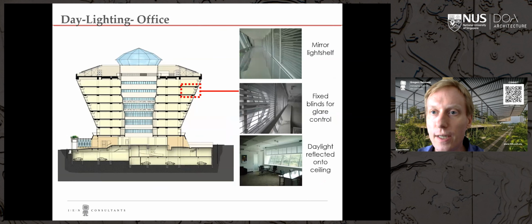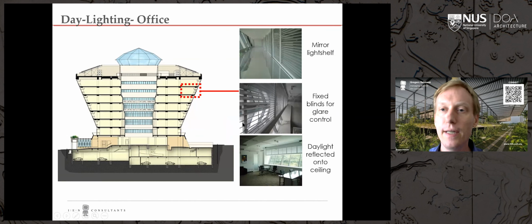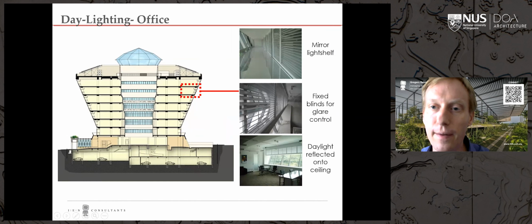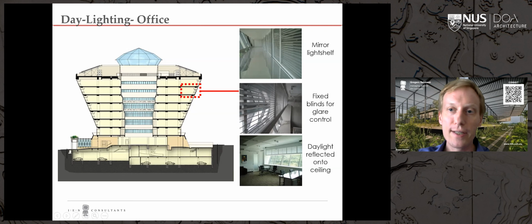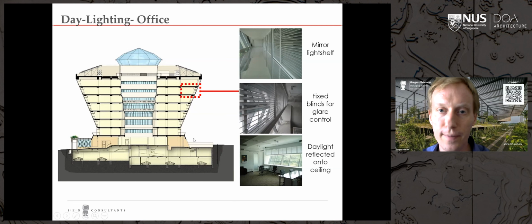Here's some photos of this light shelf design. And on the middle photo here, you can see we deliberately designed it so the windowsill protrudes about 300 millimeters further than the light shelf. So therefore, you can easily walk on this windowsill, take out a few of these louvers and go and clean the light shelf with a cloth when needed, because of course some dust will accumulate over time. So instead of going and replacing the light bulbs, because the light is very rarely on, you just go and clean the light shelves instead.